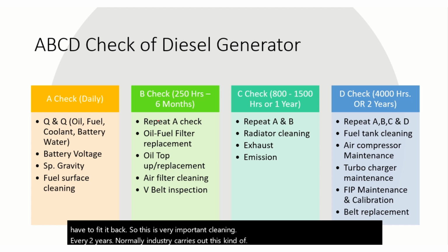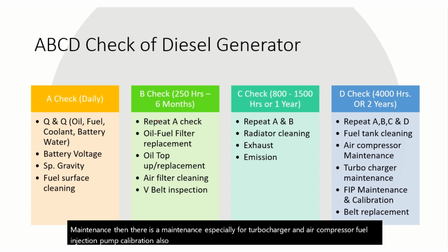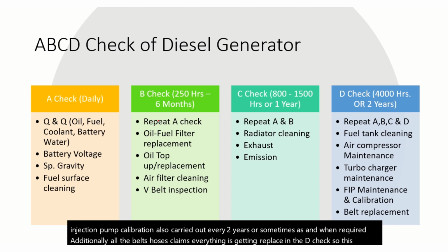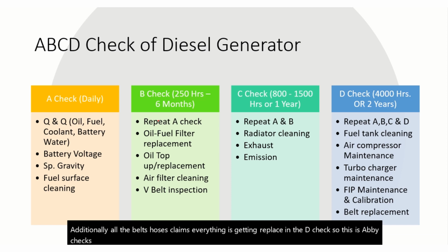Then there is maintenance especially for the turbocharger and air compressor. Fuel injection pump calibration is also carried out every 2 years or sometimes as and when required. Additionally, all the belts, hoses, clamps, everything is replaced in the D check. So these are the ABCD checks of DG sets, and this has to be carried out as per the timeline and recommendation given by the original equipment manufacturer.